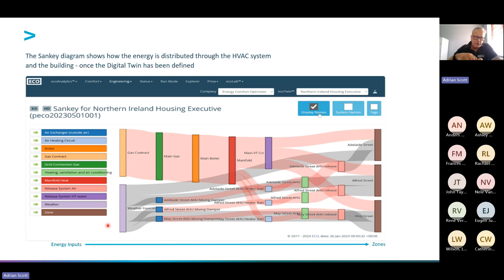The idea is taking into account the thermal inertia the system has learned from the building. We may want to enable the heat pumps during the low tariff period in the evening, because we know the building will hold and store enough temperature from that initial firing to maintain set point in the space. Set points in the eco world don't exist as we know them in temperature - this is all about energy. How much energy is required to get that specific zone up to temperature at that time and maintain it throughout the day. So the temperatures are very much in kilowatts, kilowatt hours.